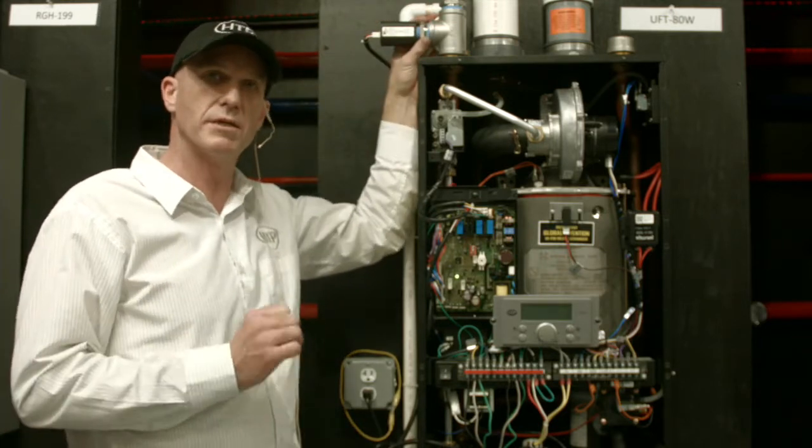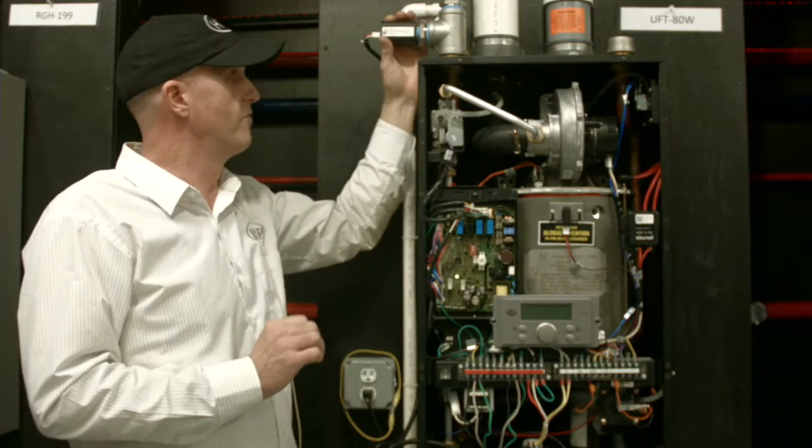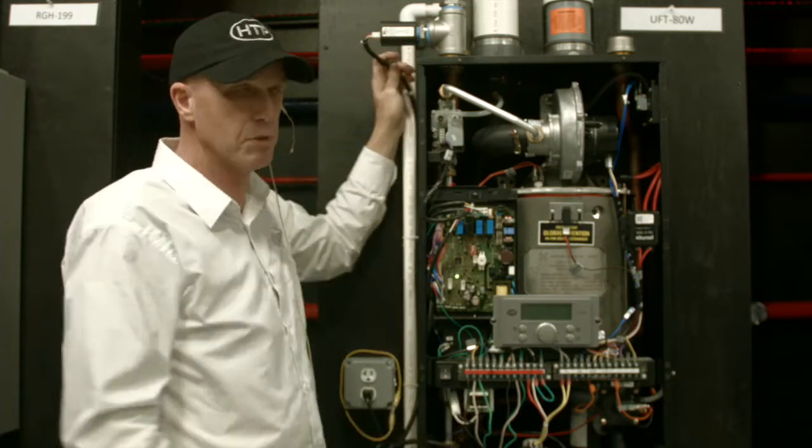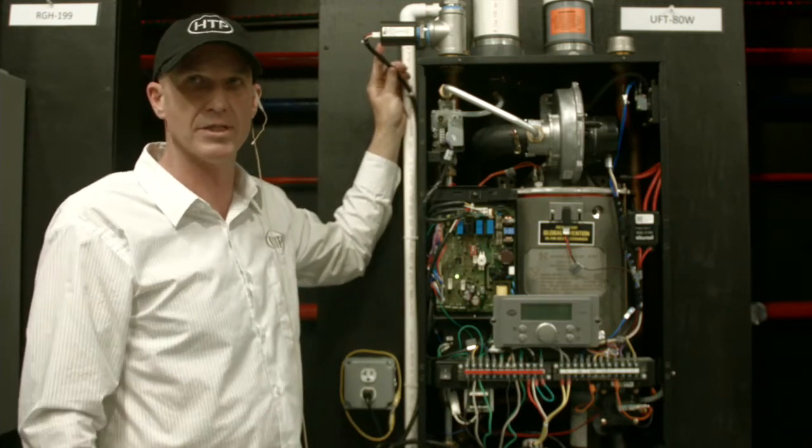We also have up here our UL 353 low water cutoff. So the machine does have a low water cutoff built in. This is a manual reset that's required by some code, so we provide a kit for this. It gives you the device, the fittings, and even the wiring harness to plug it right into our control. Makes a seamless operation.